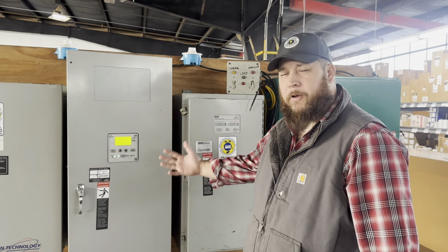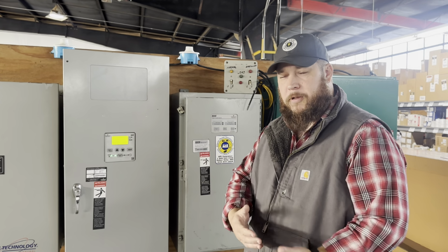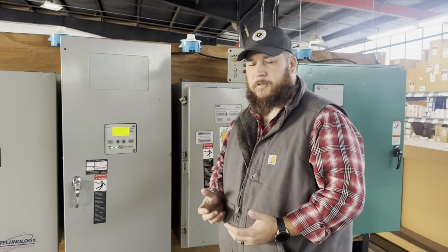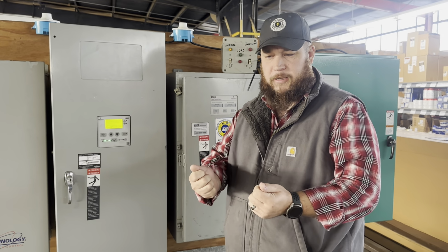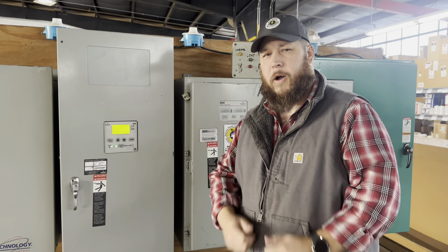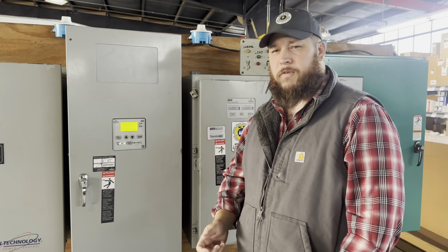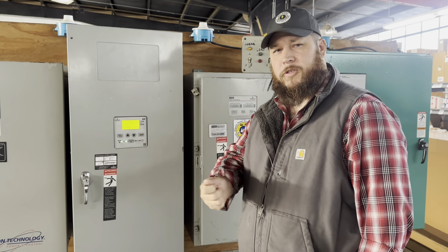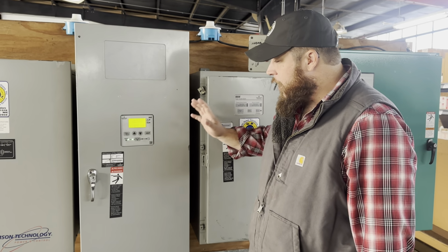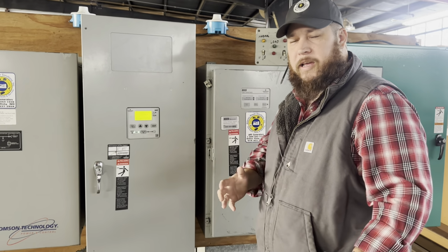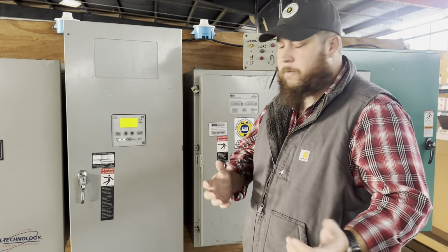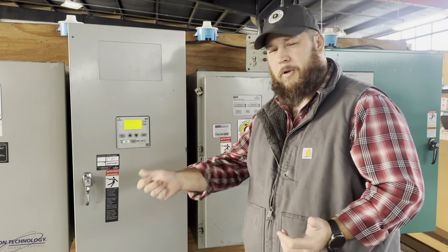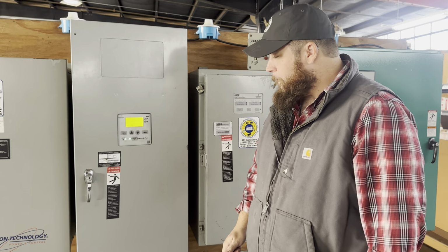Today we're going to talk about transfer switches, their purpose, and the sequence of operations. Best way to think about a transfer switch is it decides and chooses which source of power it's going to connect to. Think, if you will, if you had two receptacles and one outlet, you can only ever be plugged into one source at any given time. And so that's what this device does. It will see a power failure, start the generator, and essentially unplug from one source and plug into another source.